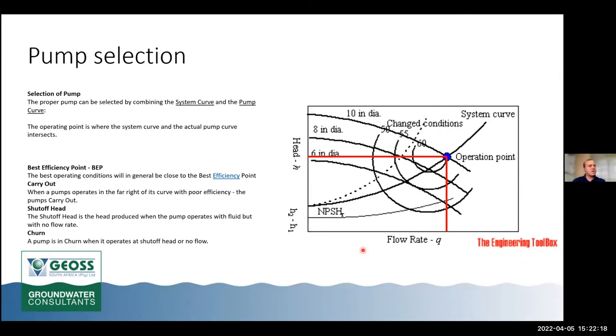To bring the system curve and pump curve together for pump selection, you literally put the two curves over each other and find an operating point — where the system curve and pump curve meet to achieve a specific rate at a specific head. Some key terminology: the best efficiency point is the optimal point within the efficiency zone; runout is where we move far to the right of the curve into very poor efficiency; shutoff head is where the system head exceeds the maximum head the pump can achieve, resulting in no flow — at that point we say the pump is in deadhead.